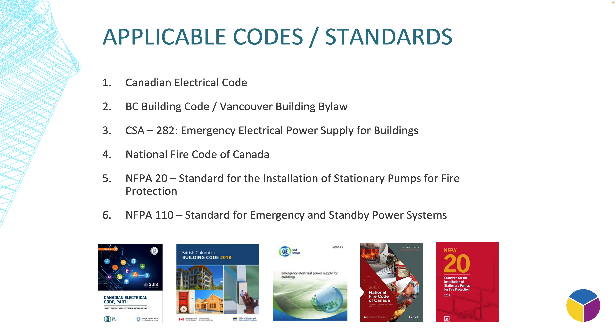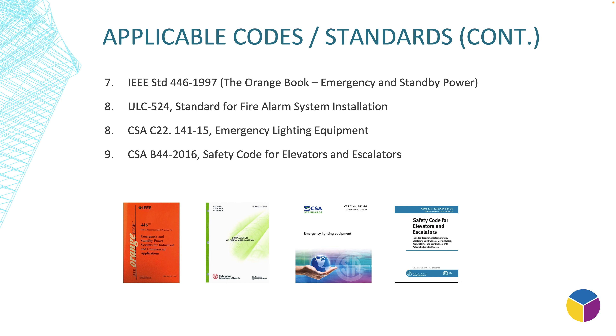The next one would be NFPA 20, the standard for fire pumps — an American standard adopted by the Canadian National Building Code and Canadian Electrical Code. There are some special requirements when you do fire pump design. NFPA 110 is the American Emergency Power System Design Standard, similar to CSA 282. We don't need to follow it in Canada, but it's provided for information.